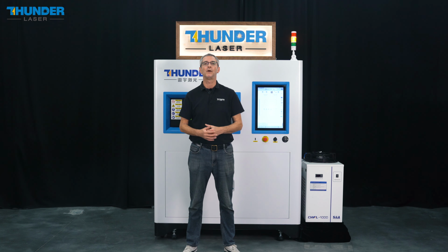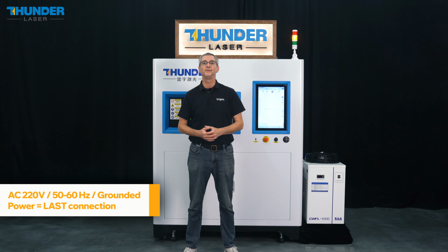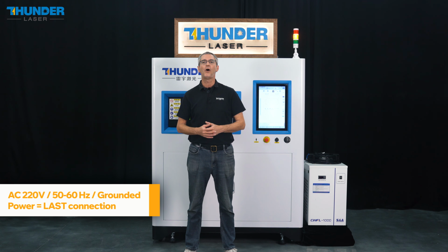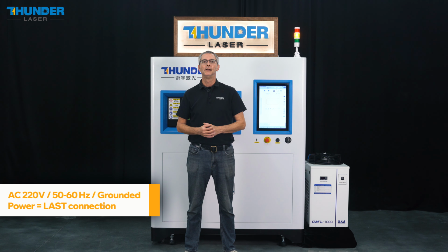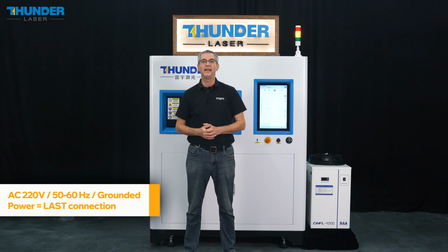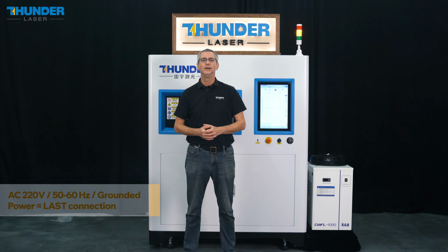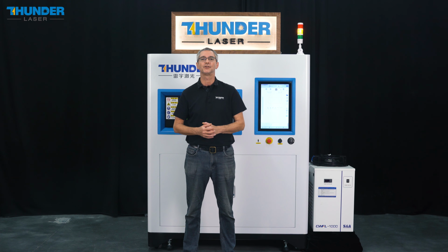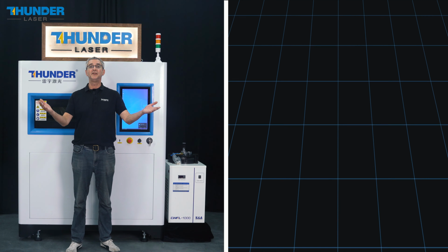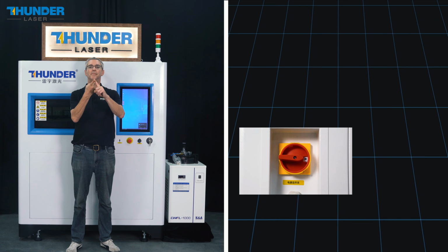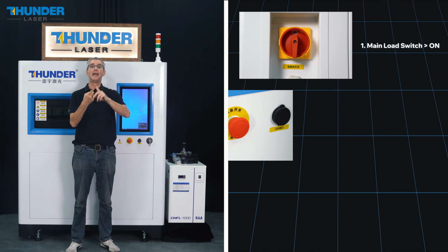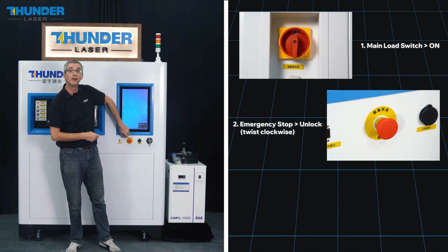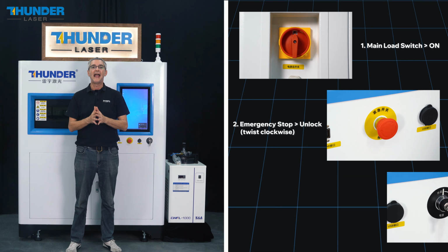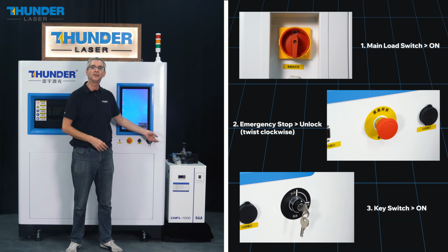Last connection, main power. Grounded AC 220 volts, 50 or 60 Hz. Always connect power last. After the chiller and gas are already in place. That order matters. You have now completed all 3 physical connections. What comes next is where most operators make the mistake that costs them their first build. 3 steps to power on, in order. Main load switch at the rear, flip it on. Emergency stop button on the front, just unlock it by twisting clockwise. And finally, insert your keys and turn the key switch on.